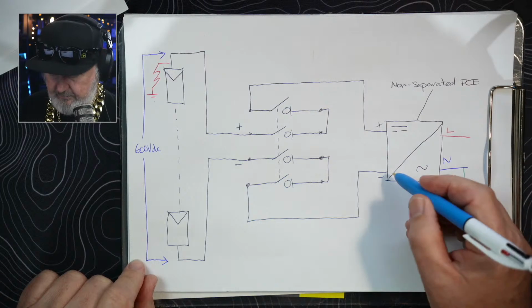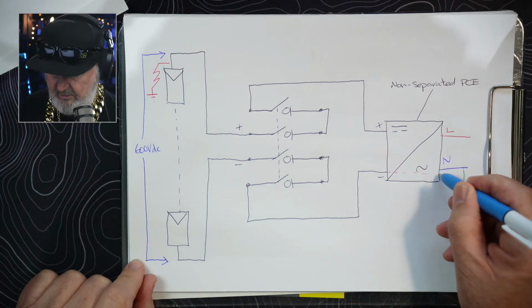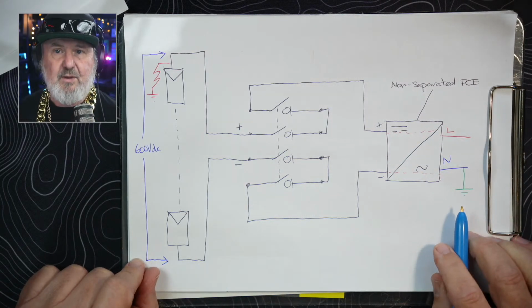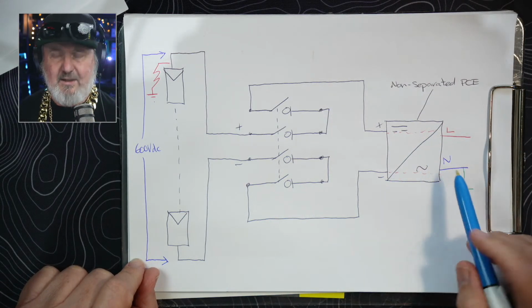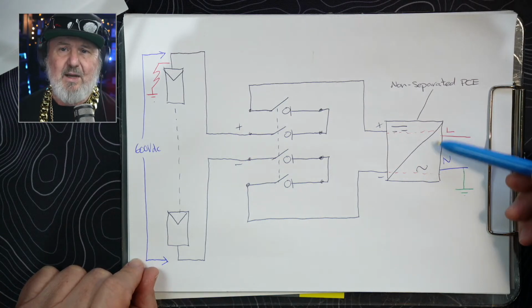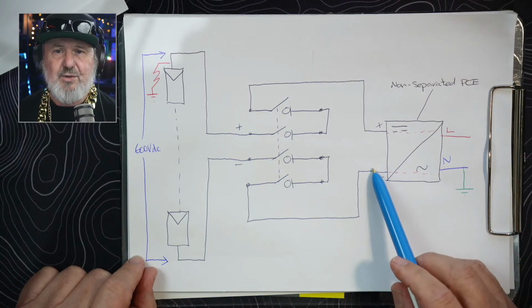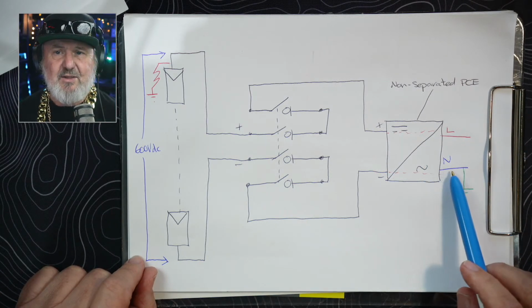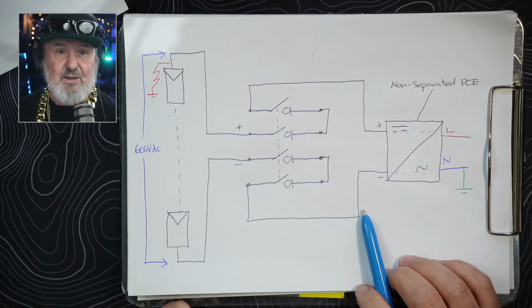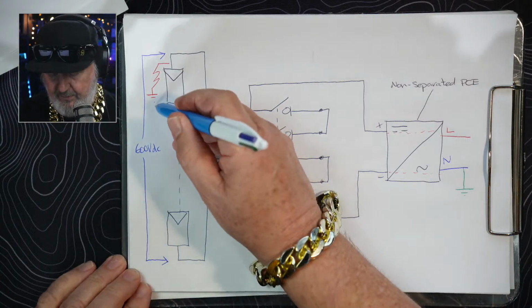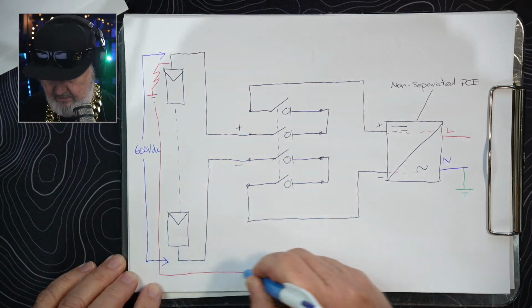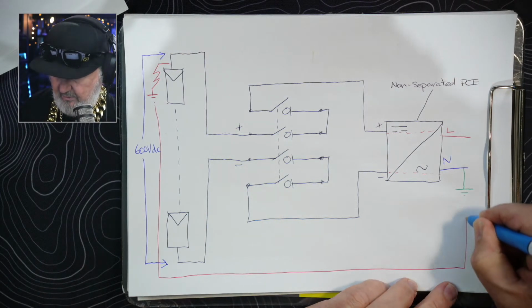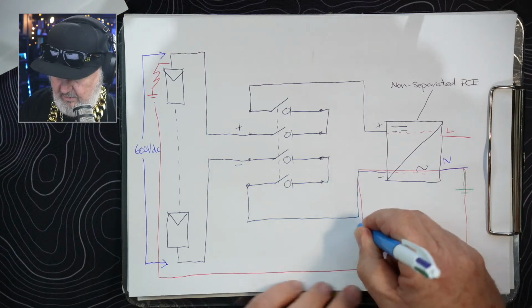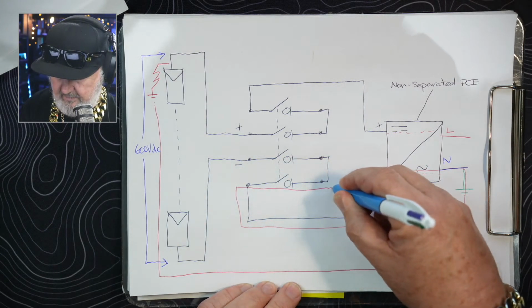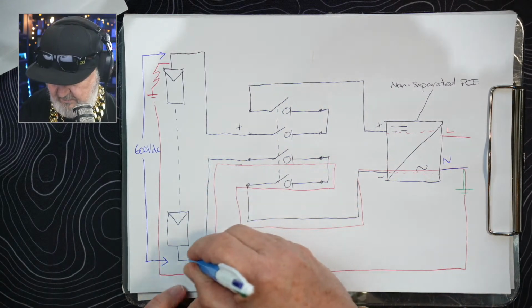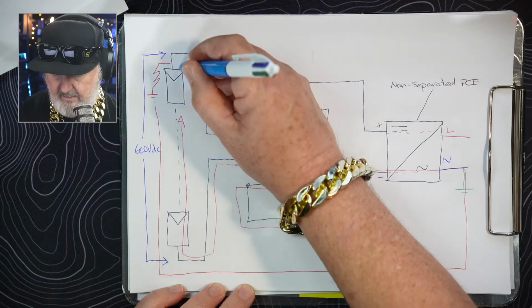When it is operating, it's effectively passing current directly through, like this. Positive through to the AC side, negative through to the AC side. And of course, these switch like 100 times a second to create AC. But at any one moment, this is true, that for instance, at this moment, the negative is connected to the neutral, and there is no transformer to isolate. So we now have a path. If we follow this fault, it's going to go down across here, and it's going to look for a path back to earth, and it's going right through my system and back up here and back to here.